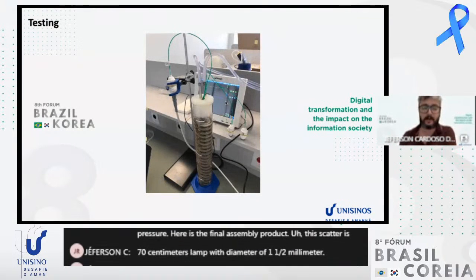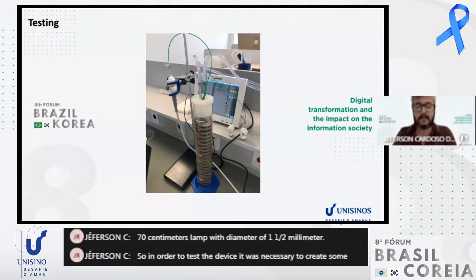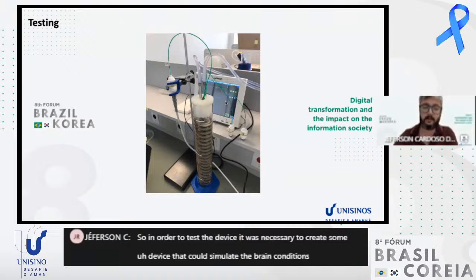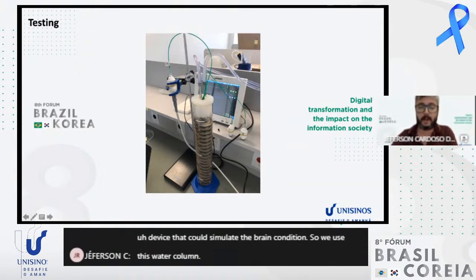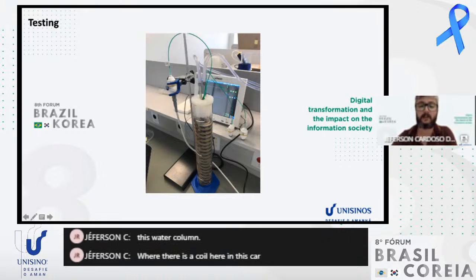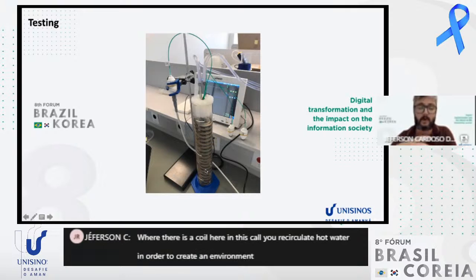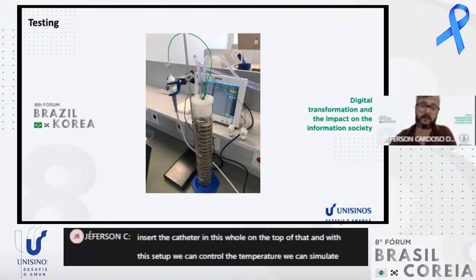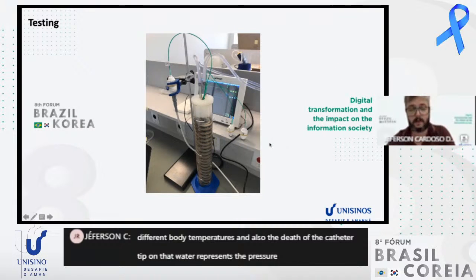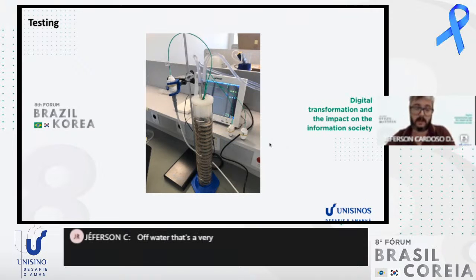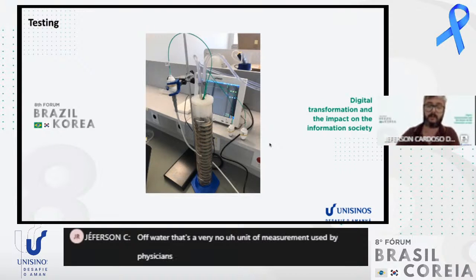In order to test the device, it was necessary to create something that could simulate the brain condition. So we use this water column where there is a coil. In this coil, we circulate hot water to create an environment with very constant temperature along the column and the water. We insert the catheter in this hole on top. With this setup, we can control the temperature and simulate different body temperatures. Also, the depth of the catheter tip in the water represents the pressure in centimeters of water, a well-known unit of measurement used by physicians in the ICU.